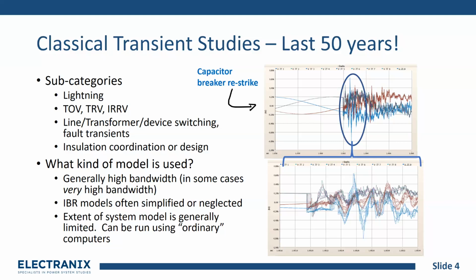And then using that tool, you can find out what is the peak voltage that you might see on that line, so that, for example, you can calculate the minimum approach distance for a live line worker. So this would be one application of an EMT tool in a classical sense. Generally, these models are very high bandwidth, so you need to have the frequency dependence of the lines. You have to have a lot of detail, especially for things like a lightning study. You model things in a lot of detail in the substation. IBR models like a solar plant or a wind plant are often simplified or even neglected in these types of studies. And the extent of the system model is also quite small, so you can run these models on ordinary computers. And these are the types of studies that many people think of when they're talking about EMT studies.